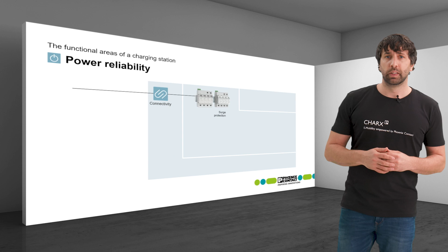Combined lightning current and surge protective devices, so-called combined type 1 and 2 arresters, can disconnect up to 50 kA. Simple type 2 arresters up to 40 kA are sufficient for home chargers.